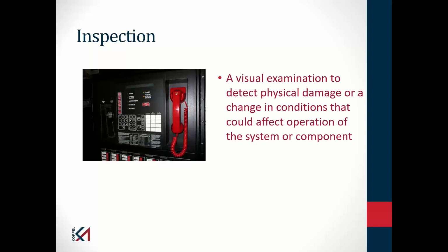Let's now look at some of the requirements in NFPA 25. You will find a chapter for each type of water-based system. So there'll be a chapter 5 on sprinkler systems, chapter 6 on standpipe systems, chapter 8 on fire pumps, and so forth. At the beginning of each of those chapters, there will be a summary table of what all the tasks are: what are the inspection activities, what are the test activities, what are the maintenance activities, and what are the frequencies for those activities.